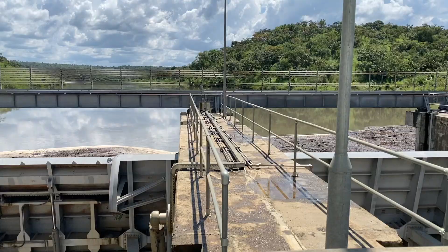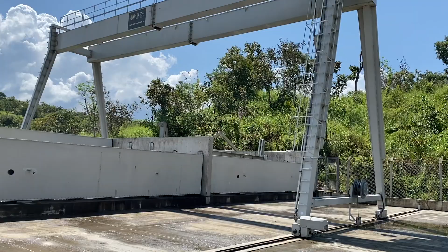Then down we have what we call the main inlet valve. The main inlet valve is like a tap - when you want water, you open the tap, and that's how the main inlet valve works. When we want to start our unit, we give a start signal through our SCADA, then the main inlet valve opens. The difference with a tap and ours is that here it opens automatically - we have hydraulic oil which goes to the main inlet valve and opens it.